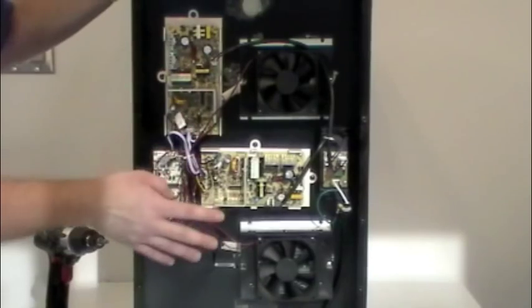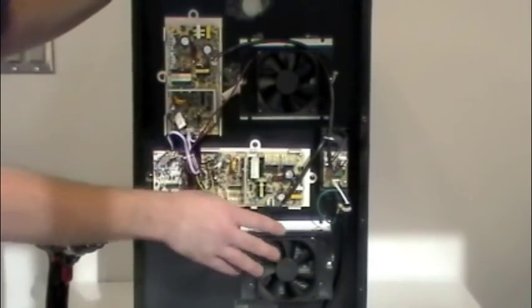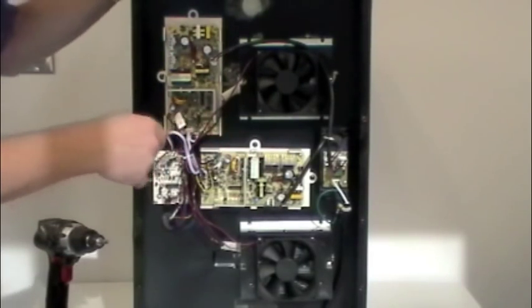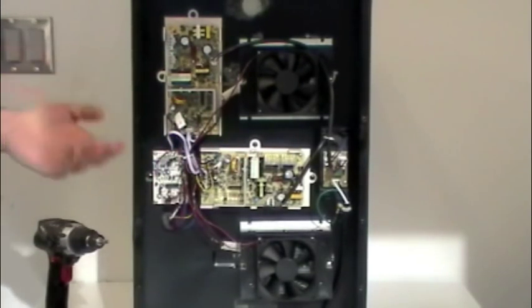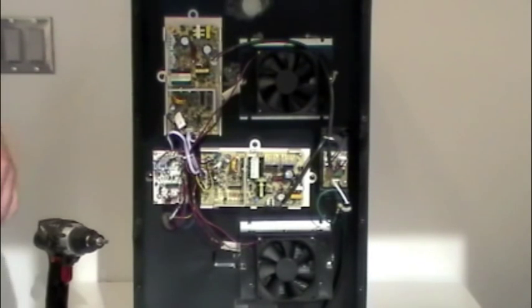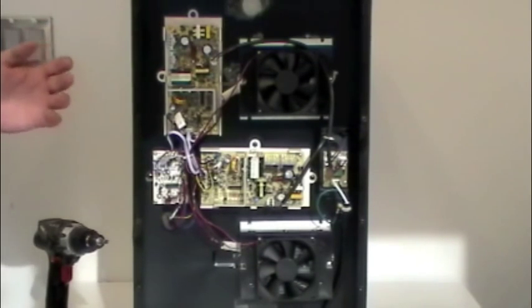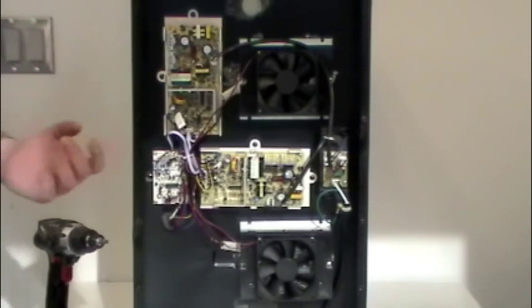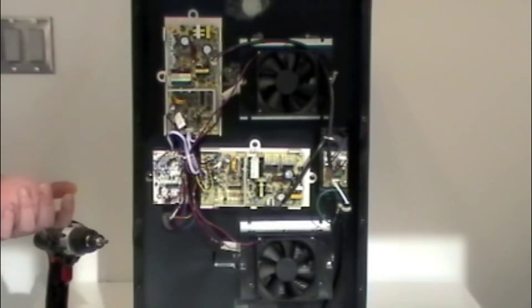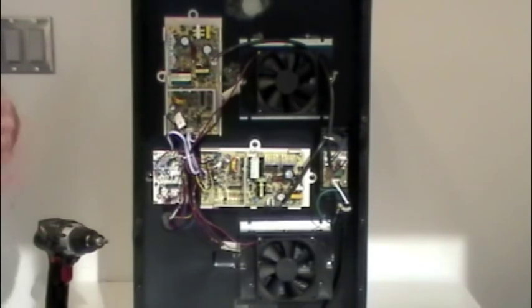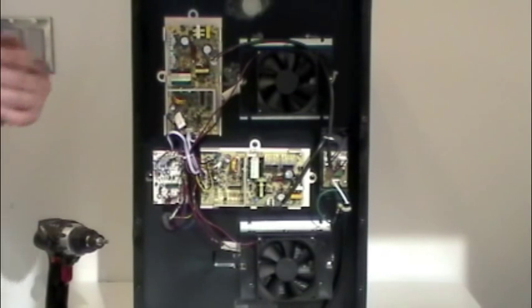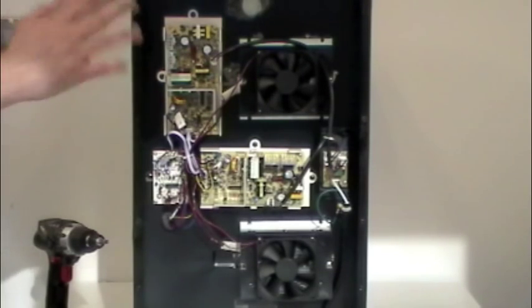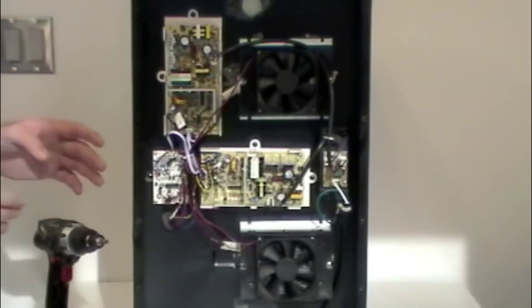We've talked about our fans. We've talked about our input over here. We've talked about our circuit boards and what they do. And occasionally also, by the way, on these circuit boards, you're going to find that the board won't power up. And it obviously has a defective component. We've got scorch marks. We've got arcing. It's plainly obvious that something on the board has failed. And at that point, you're just going to replace the board. Because with an obvious burn or a failed component or a blown resistor cap, we know the board's bad. So, we're just going to replace it.